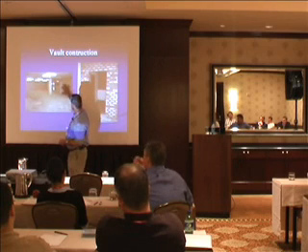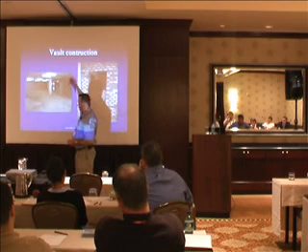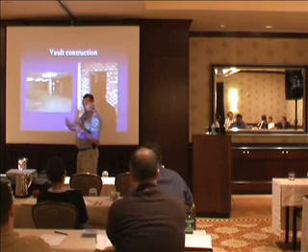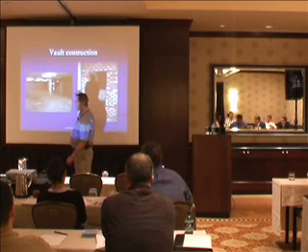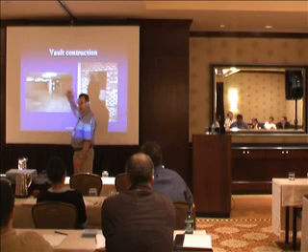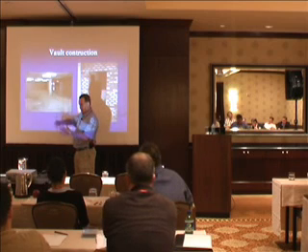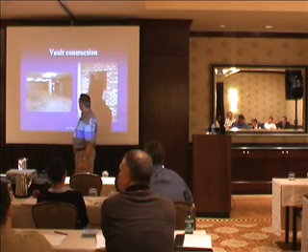The reality is we have all the electrical cables coming into the building in the room behind that, and that is probably the most risky area in our vault. So that's the main purpose of the Durasteel in reality, to protect the vault from the potential risk of all the cabling catching on fire. But also it's going to look very nice too.